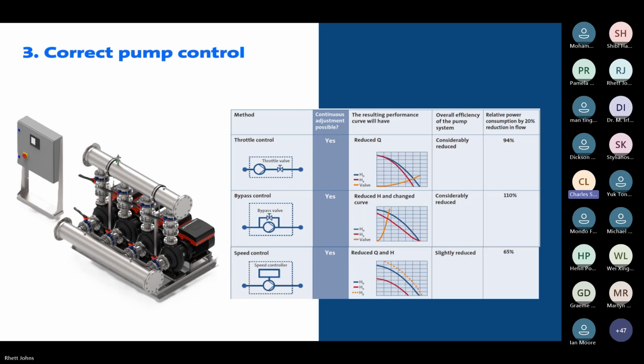So I said these are more traditional methods of pump control. The third method we would consider the most efficient method, and that is speed control. And you can see this here. This is the most efficient because we can reduce the speed depending on the demand of the system, reducing the flow whilst not putting additional pressure into the system. But most crucially, we're only using the power that we need.